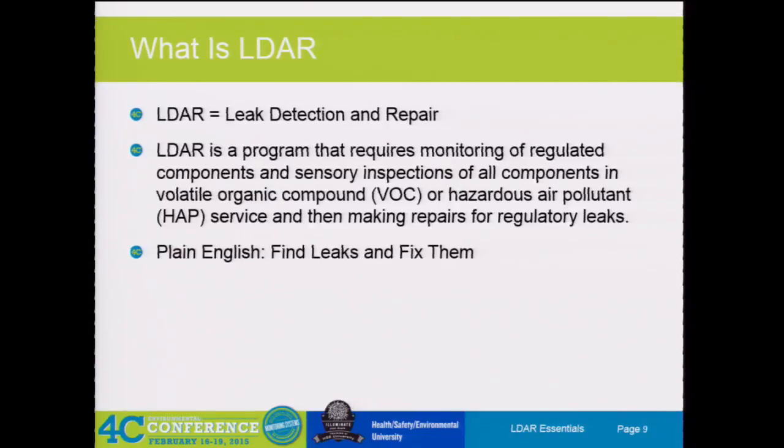But with that, now, as you can see, we started out originally, so how many folks are applicable to VV in here? NSPS VV? Okay, only one. How about HON? Okay, there we go, a few more. So we started out at a 10,000 ppm leak definition. Then VV came out, and VV stepped down to where now you have a 500 ppm leak definition.